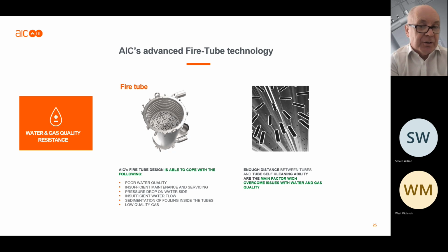And on the flue side, there are larger flueways, and you've got down-firing burners, so you're pushing the gases through it. Also, the gases condense as they go through the tube as it gets cooler at the bottom, so it flushes out any build-up of gas residue out through the fire tubes, out through the condense dish, and straight to waste. Okay, so that greatly reduces the possibility of premature failure within the heat exchanger through poor water quality or gas quality.